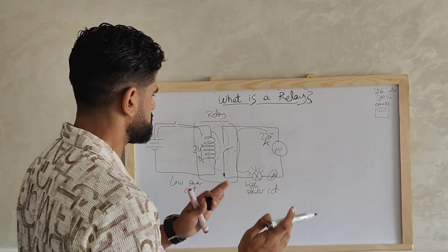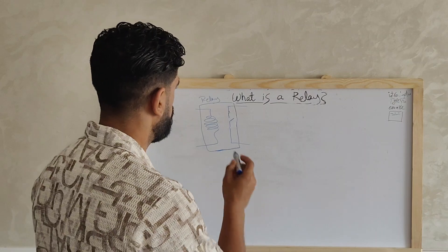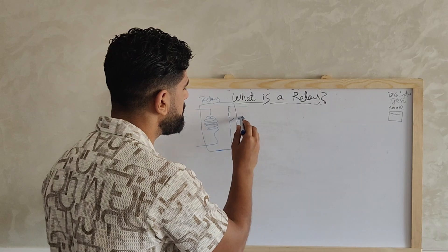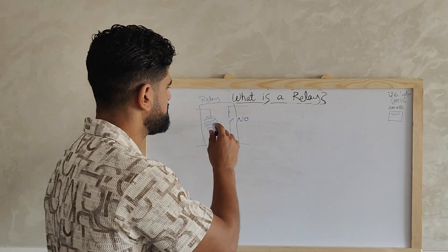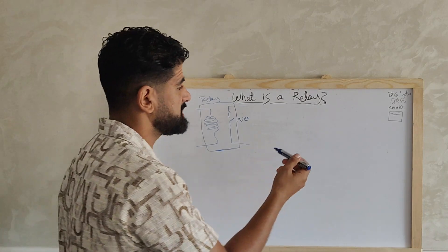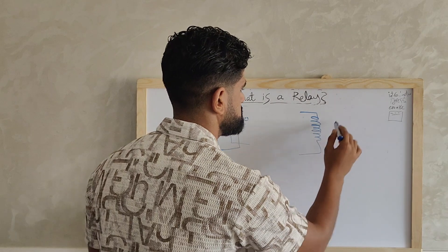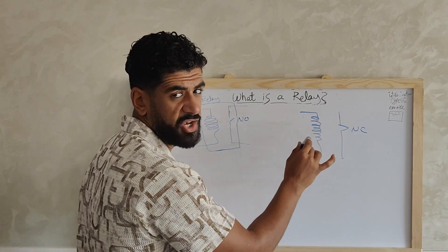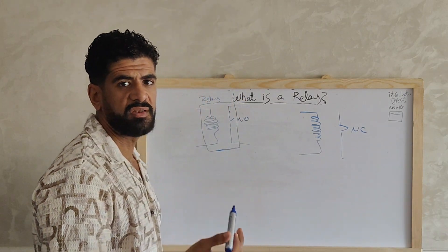So as we can see, we have two circuits: low power and high power circuits. Inside our relay we have the coil and the contact. This contact is a normally open contact, which means that it's open in its primary status. When this coil is energized, this contact will be closed. There is also a normally closed contact — when the coil is energized, this contact will be open, and we can use it in other applications.